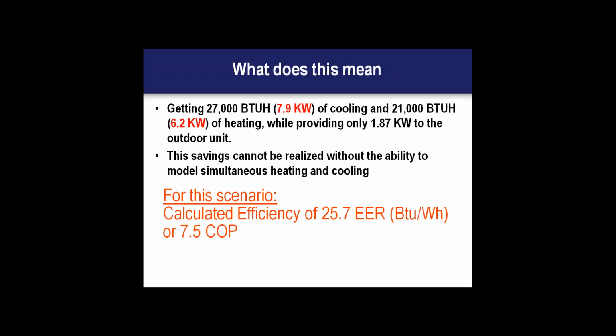We've only spent 1.87 kW at the outdoor unit. Again, that includes the compressor energy and the condenser fan and some minimal losses for piping. That equates to a calculated efficiency at this hour of 25.7 EER or 7.5 COP. Again, this is an idealized situation because we're close to that 50-50 balance point. And again, that's going to be your highest efficiency level.